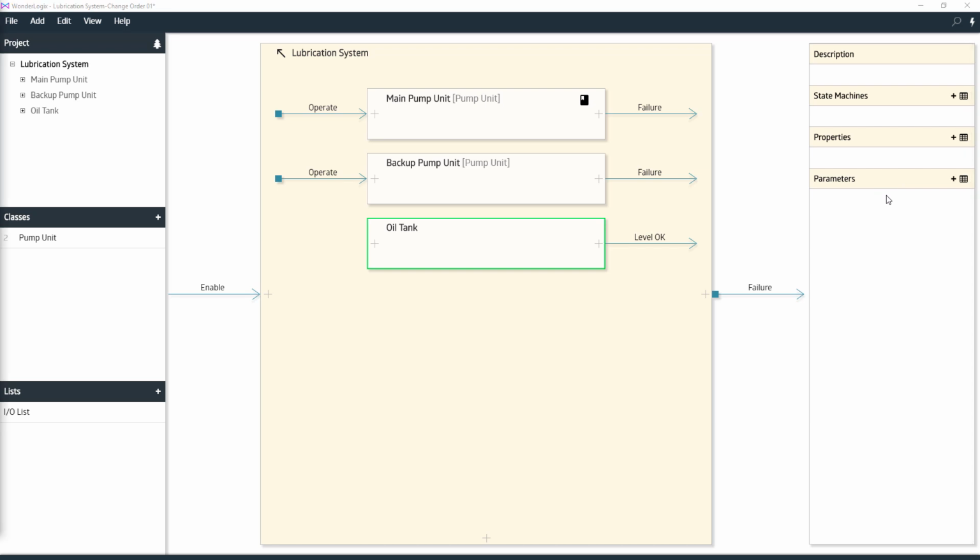A parameter is an item that can hold a value. It's a variable with a name. It can hold a value, and it is not updated by the model. Later you'll find out that properties can be updated by the model, but parameters are not. They can, however, be set to be updated by the HMI. For example, we might create a parameter that has a set point or a recipe number that we want the operator to be able to update live from the HMI. But it is useful to hold a value here with a parameter name so we can use the English name within our logic to help improve understanding and make it easier to update all in one place.